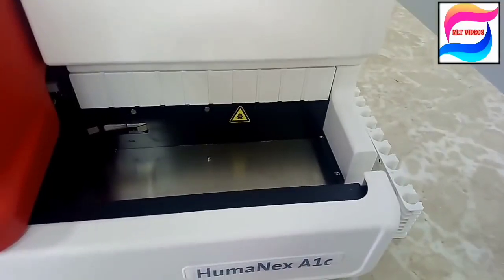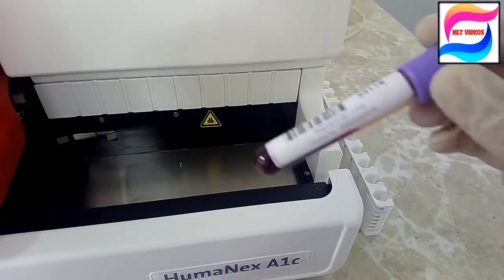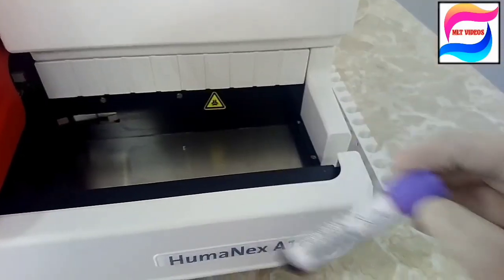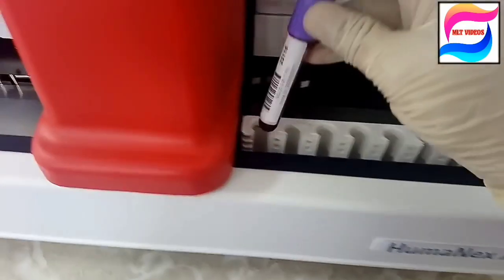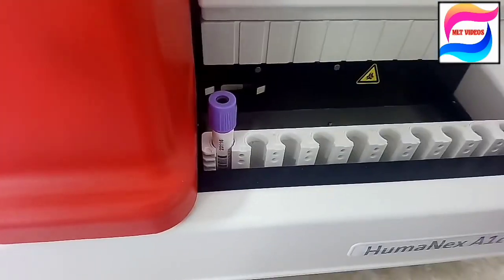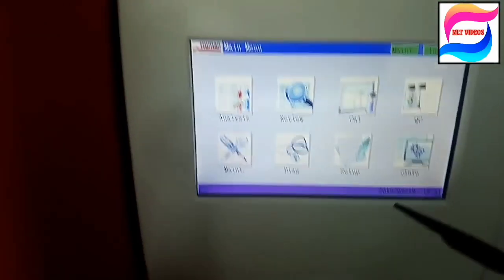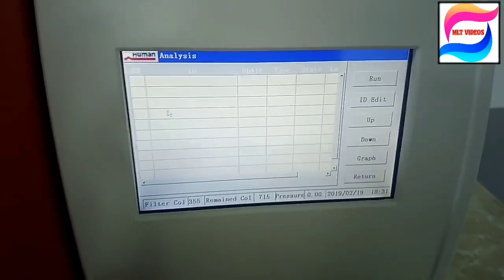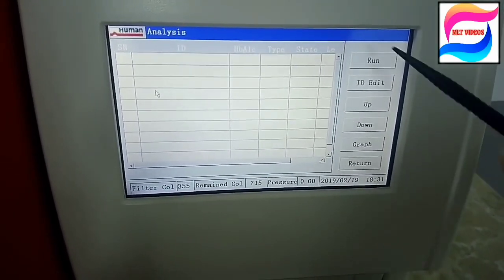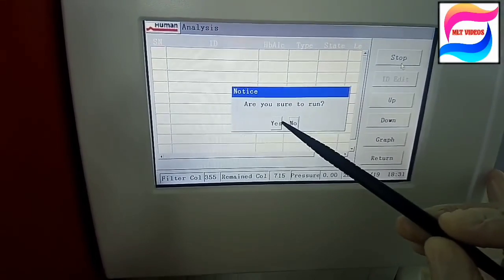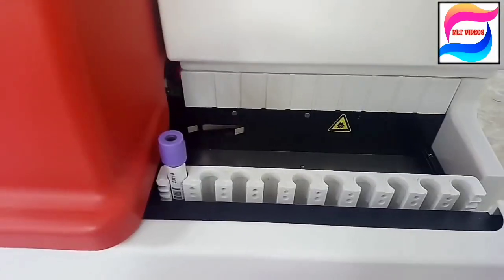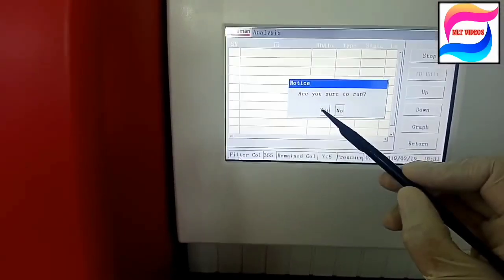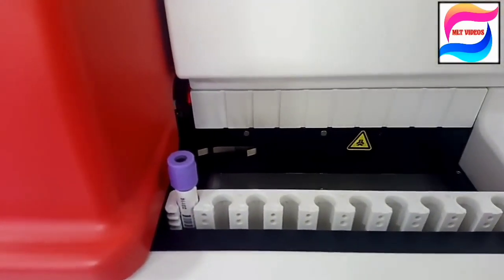Here right side we will keep the sample and it will go inside the machine. And then from left side there is exit of the sample. So like that we will position the rack and we will keep the EDTA whole blood tube. And just try to mix the sample before keeping. Sometimes plasma, if long time sample is kept, plasma will separate. So try to mix the sample properly. As there is barcode, so no need to enter the name. Just we will click the run. If there is no barcode on the tube that time we will enter manually. So just we will click yes and automatically it will go.